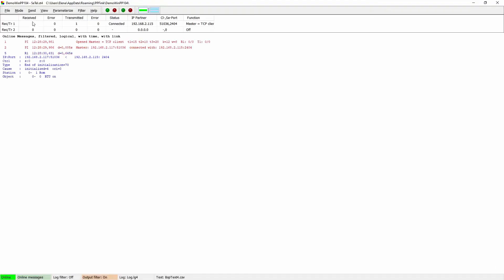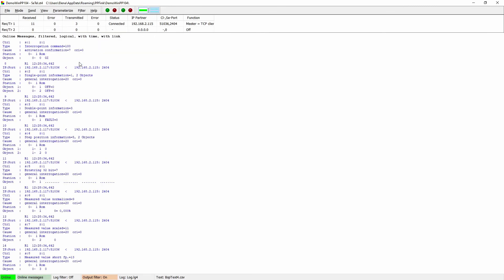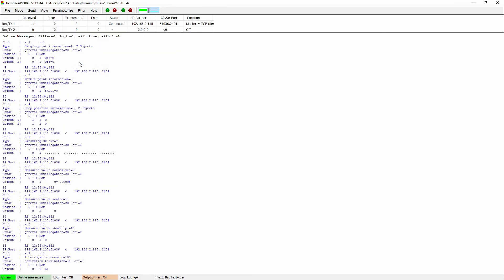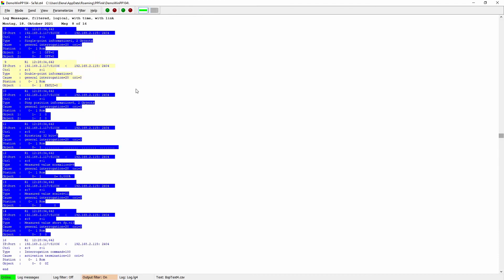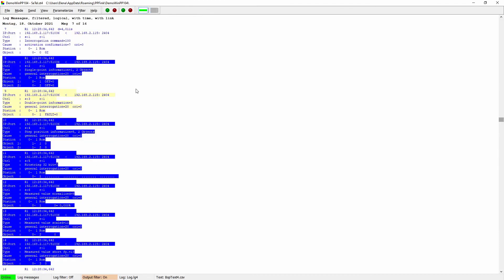If we now initiate a general interrogation from within a program like WinPP-104, we will receive the following messages from our IEC 60870-5-104 server, showing that all configured objects, except the one excluded double point information object, are sent.